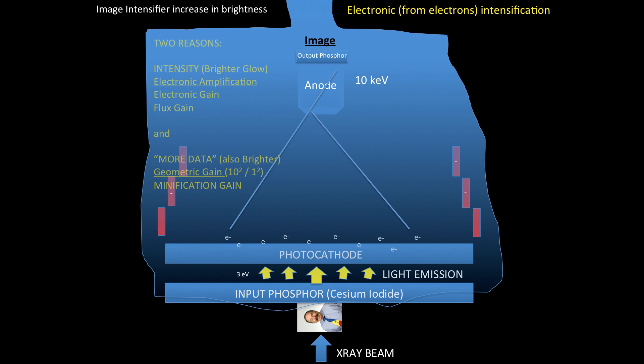The image intensifier then, it's important to realize that it creates an increase in brightness. This increase in brightness has two main components. The main components are the component that relates to the intensity, so that's the electronic amplification, the electronic gain, or the flux gain. All those are the same, different terms for the same phenomenon.